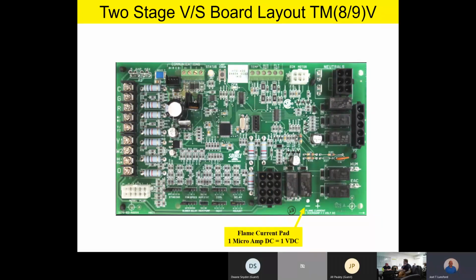All right, now here's our flame current pad. You'll notice that it's in a little different position than it was on some of the previous products that we've talked about. In this particular case, the flame current pad is at the bottom of the board, but don't sweat that. It's the same function as every other flame current pad we've talked about. So instead of having a special meter for reading flame current, you just take your plain Jane voltmeter that you've got in your truck, put it on DC volts, and then go down to that flame current pad. 1 microamp DC is equal to 1 volt DC. So on your meter, you're going to read 1 volt DC for every microamp DC that the flame sensing circuit is putting out. So this is very, very handy.